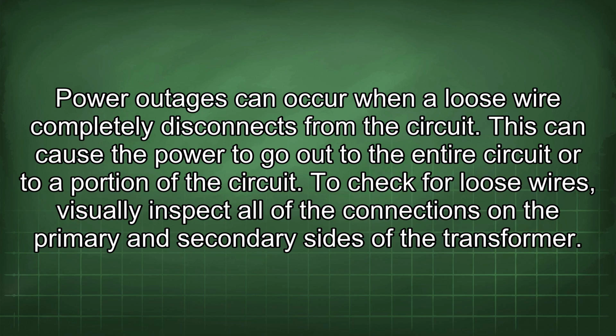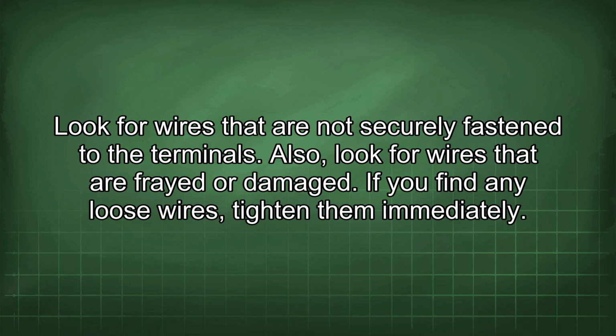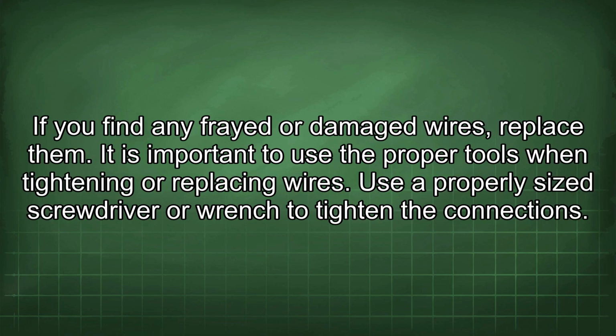To check for loose wires, visually inspect all of the connections in the primary and secondary sides of the transformer. Look for wires that are not securely fastened to the terminals. Also, look for wires that are frayed or damaged. If you find any loose wires, tighten them immediately. If you find any frayed or damaged wires, replace them.